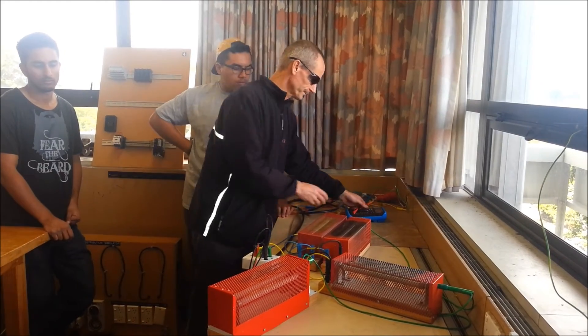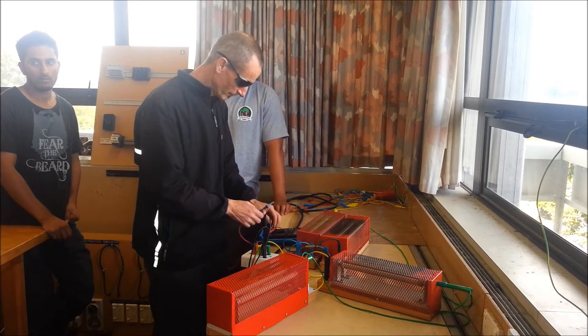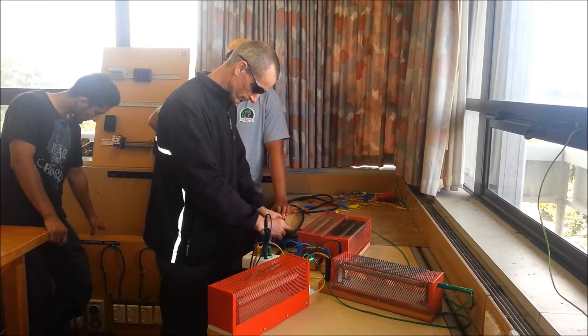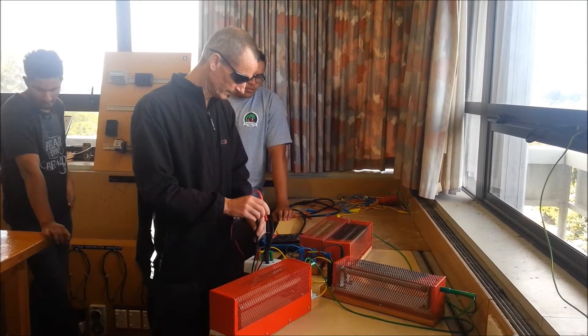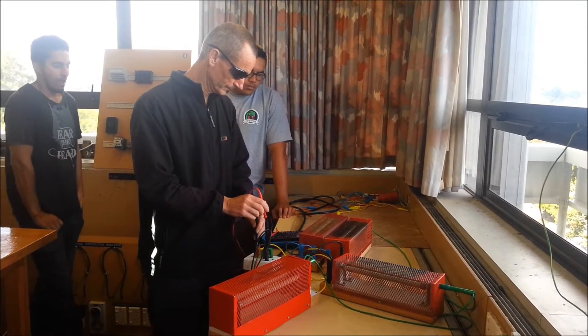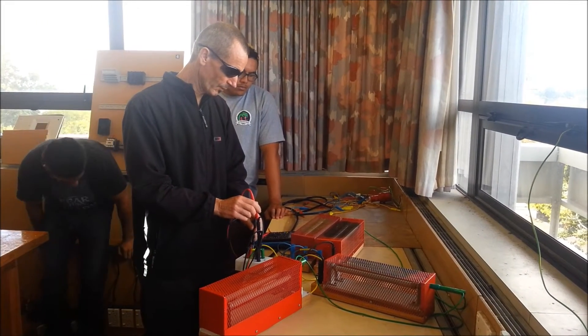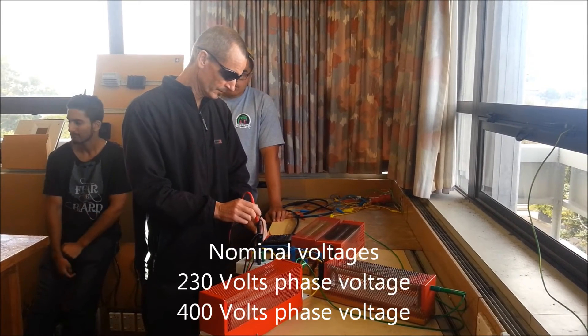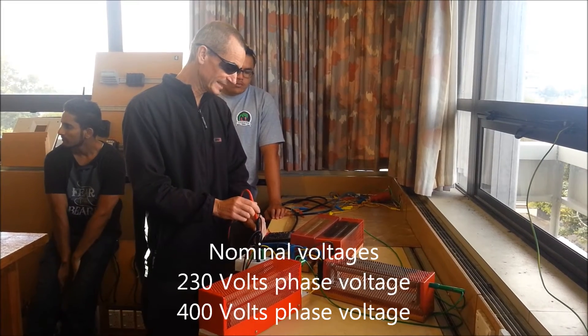Voltages. Neutral to red phase voltage, red to neutral, 233. Neutral to white, 234. Neutral to blue, 237.